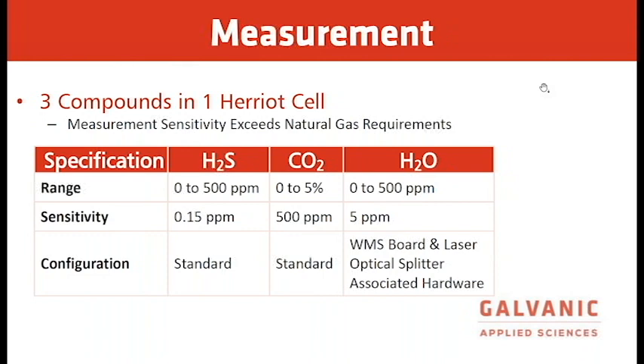This one here is a nice summary, showing the main measurements of our AccuLase. We can measure all three components, as Ian mentioned, in just one single unit, one single cell. For example, for the natural gas value chain, we can do H2S 0 to 500 ppm with an LDL of 0.15 ppm. For moisture, we can do 0 to 500 ppm, and the LDL is 5 ppm here. For the CO2, we can do 0 to 5% with an LDL of 500 ppm. Again, everything is one single unit, one single cell. Other ranges can obviously be offered as well, depending on the application. AccuLase can also support multi-stream measurements for all these components using the same unit, which is another advantage and a good feature of this product.